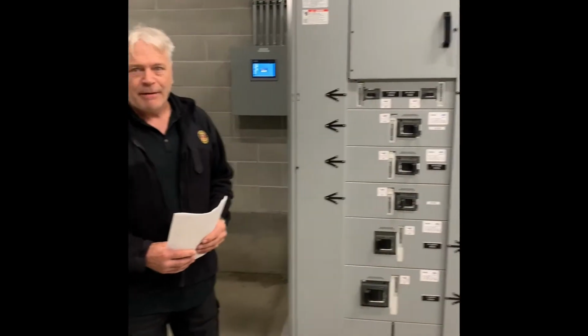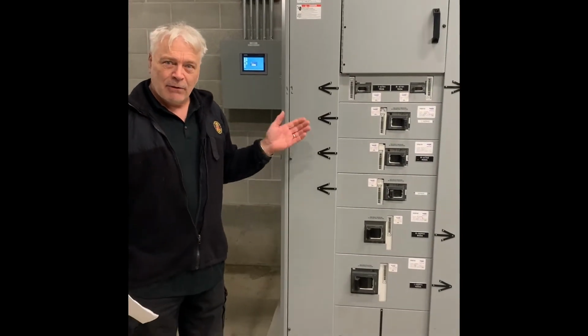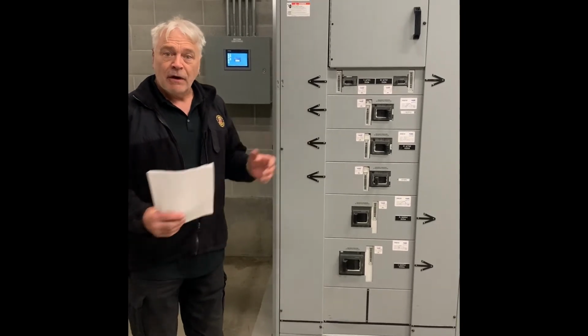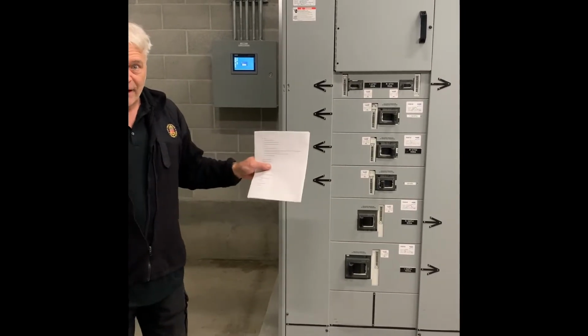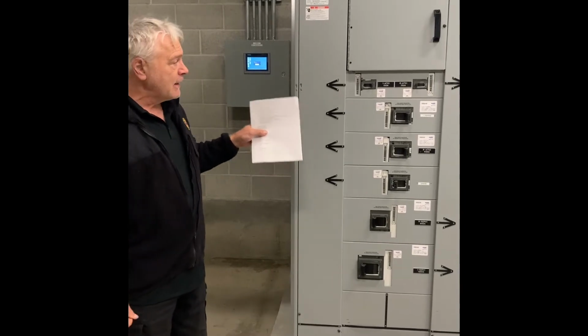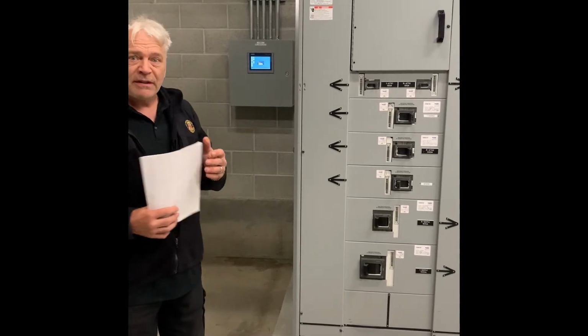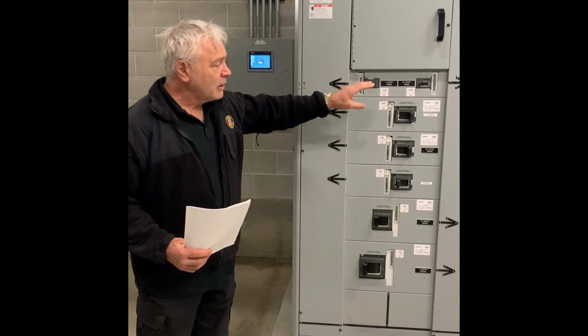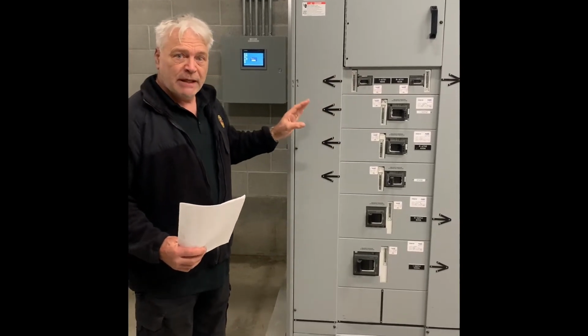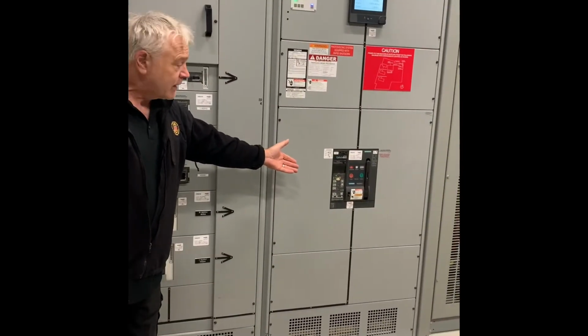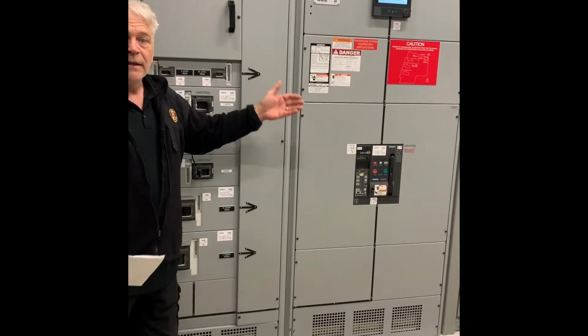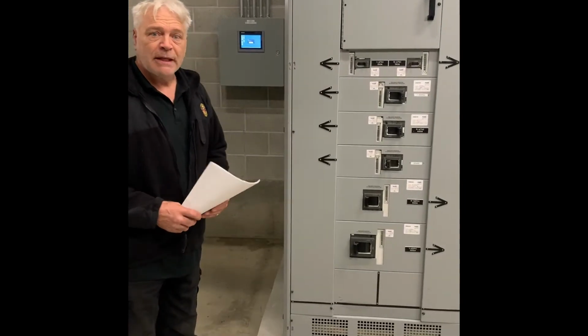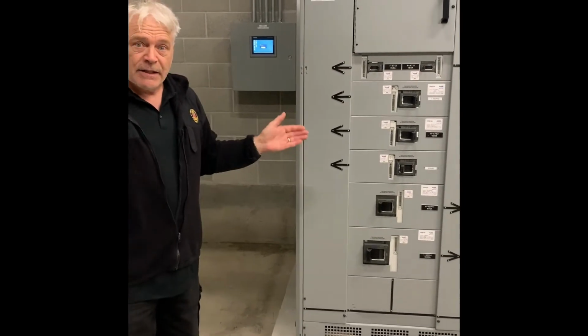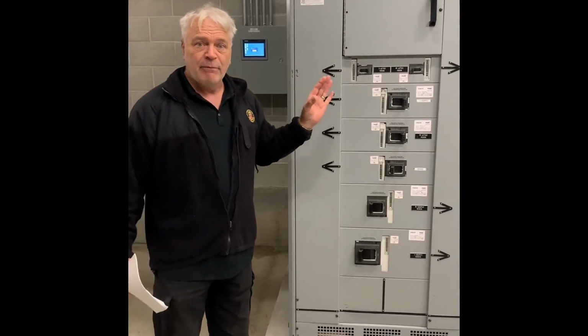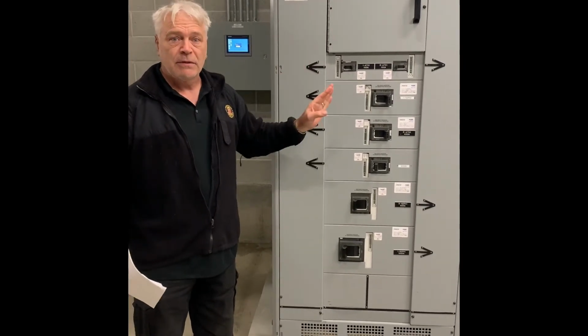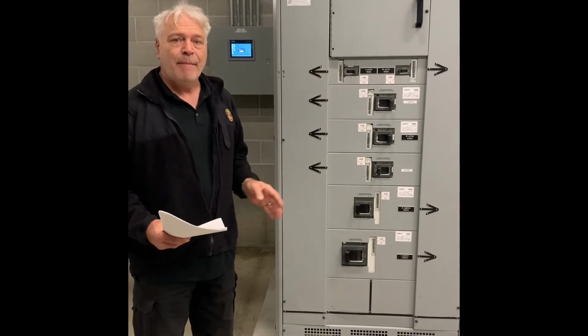Okay, now we're going to talk briefly about maintenance. Maintenance is done by authorized and qualified personnel only. All the maintenance procedures will be clearly identified in the O&M manuals. Each one is specific to the type of product. For example, these smaller distribution breakers have different maintenance procedures than this larger molded case breaker. The lubrications are different. The procedures for the maintenance are all different. A maintenance schedule is important. All of the maintenance information, lubrication, maintenance schedules, and maintenance procedures is clearly identified in the O&M manuals.